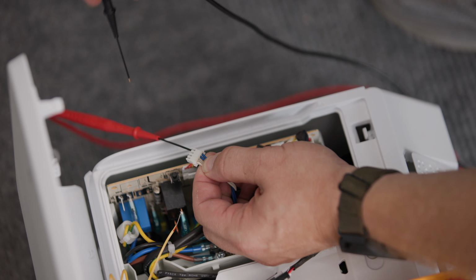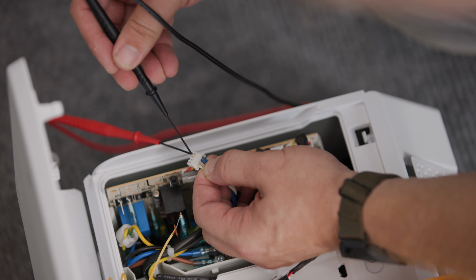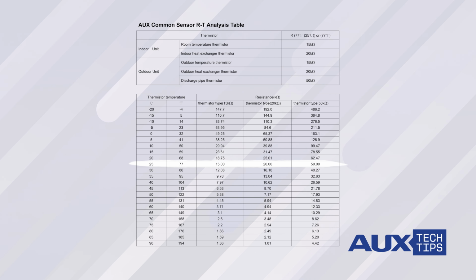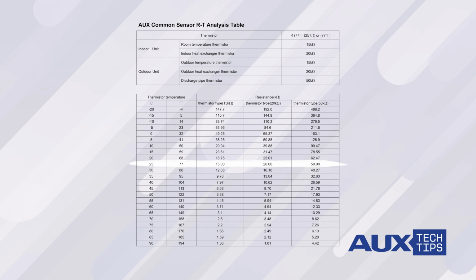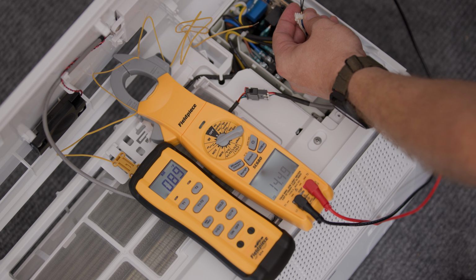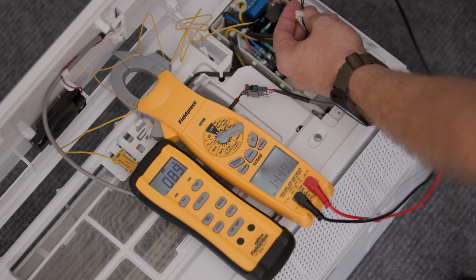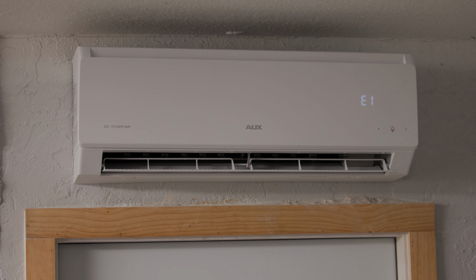Before testing, check the current room temperature with a thermometer. Refer to the sensor chart in the AUX service manual to find the expected resistance for your thermistor at the current room temperature. For reference, at 77 Fahrenheit, you should see 15 k ohms for your indoor ambient or outdoor ambient sensors. Compare your multimeter reading to the sensor's chart value. If it matches, the thermistor is likely fine. The error code may point to another issue.